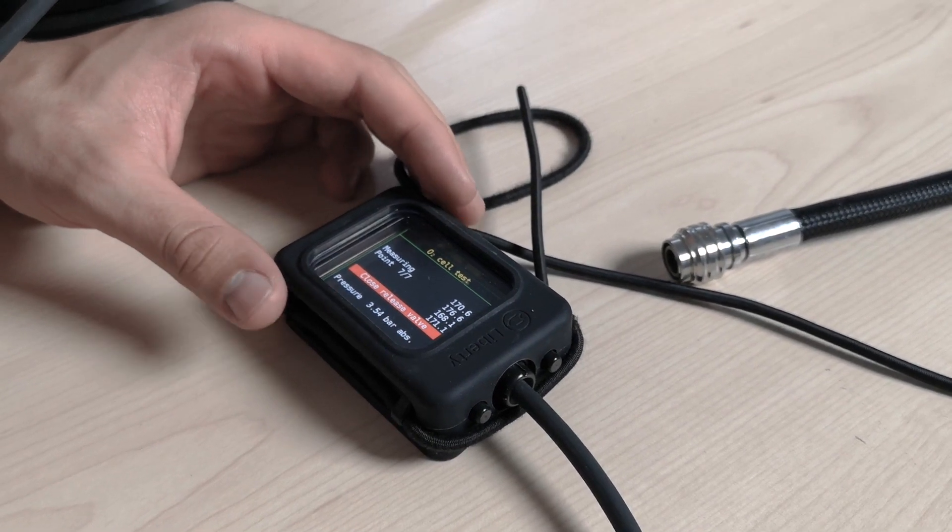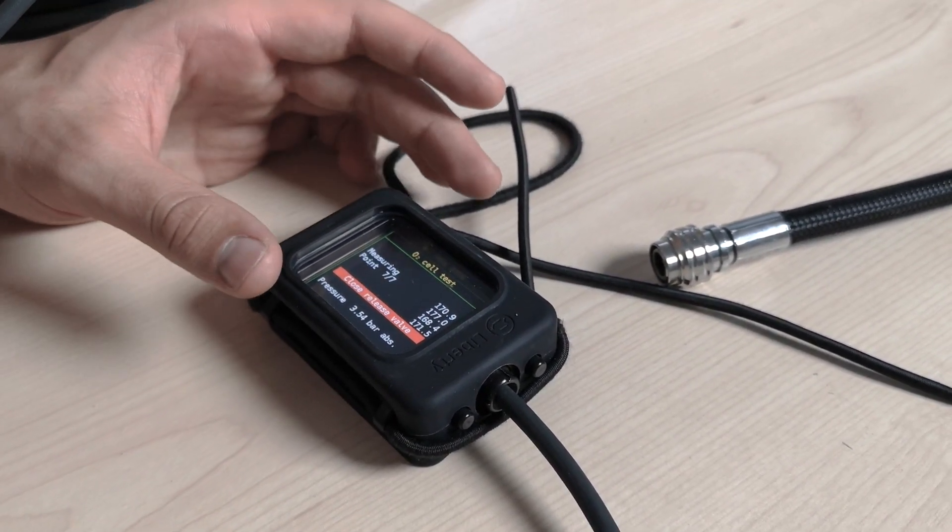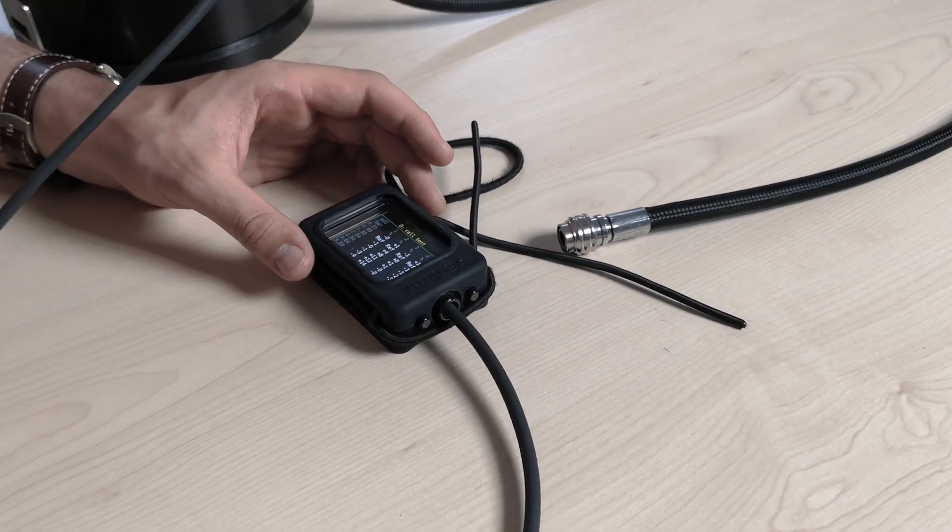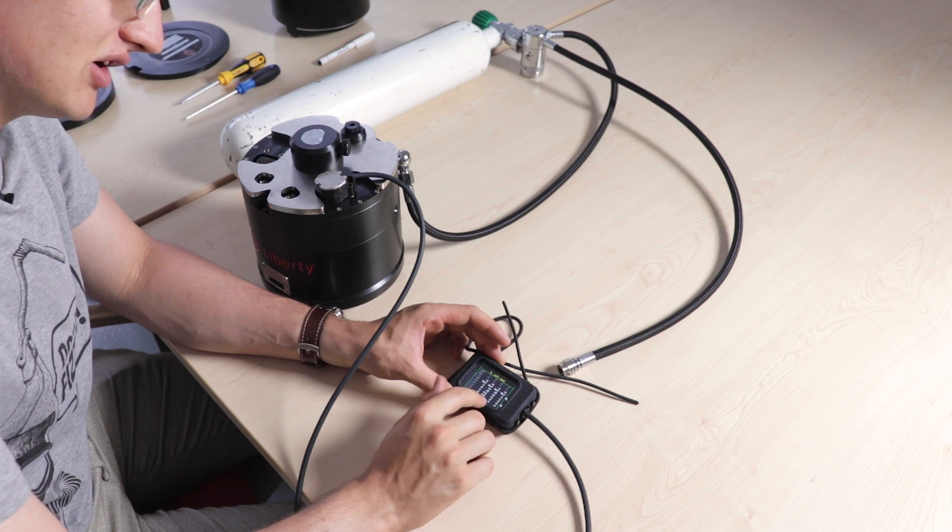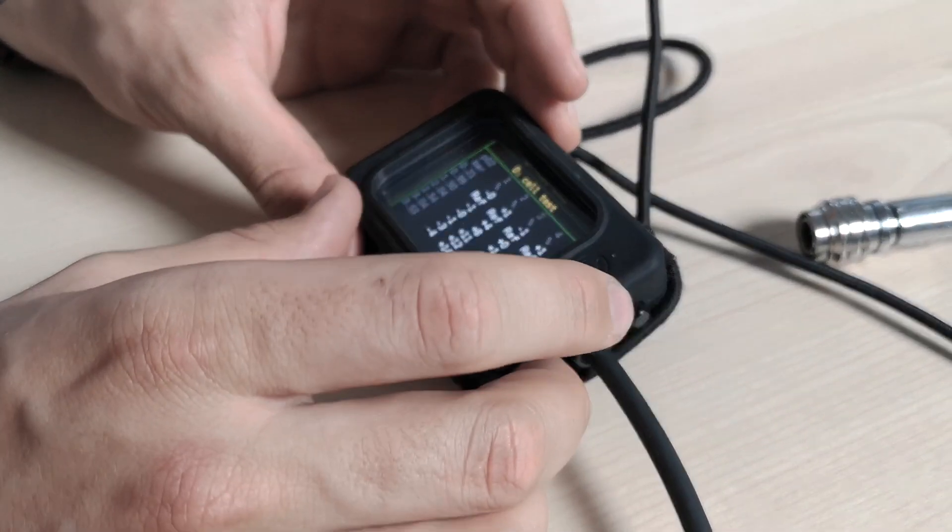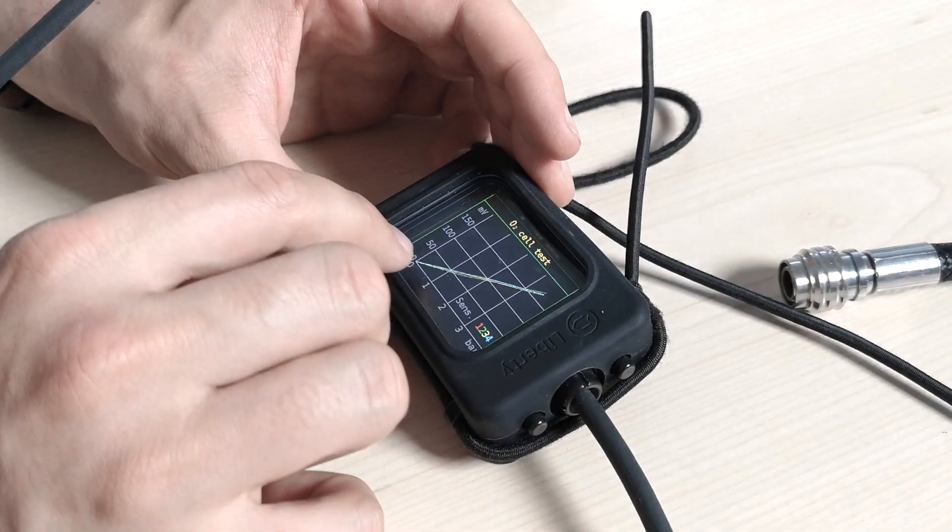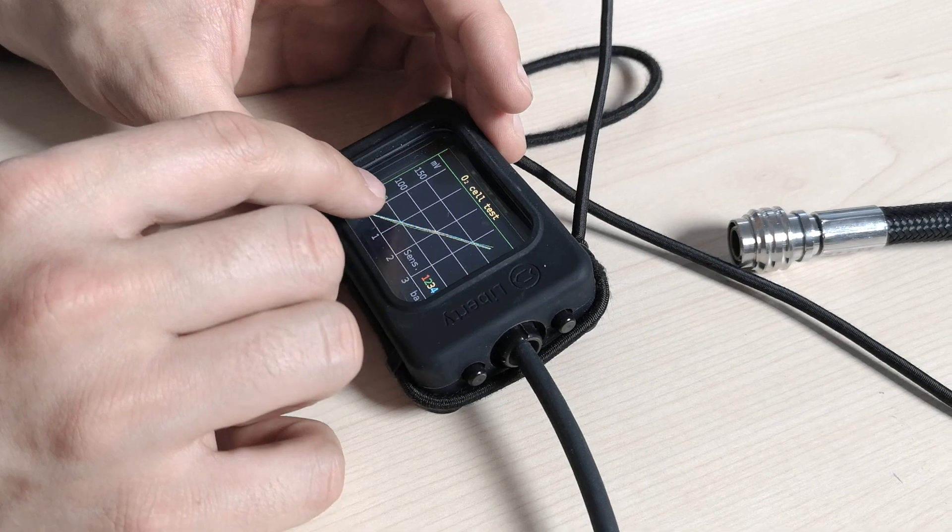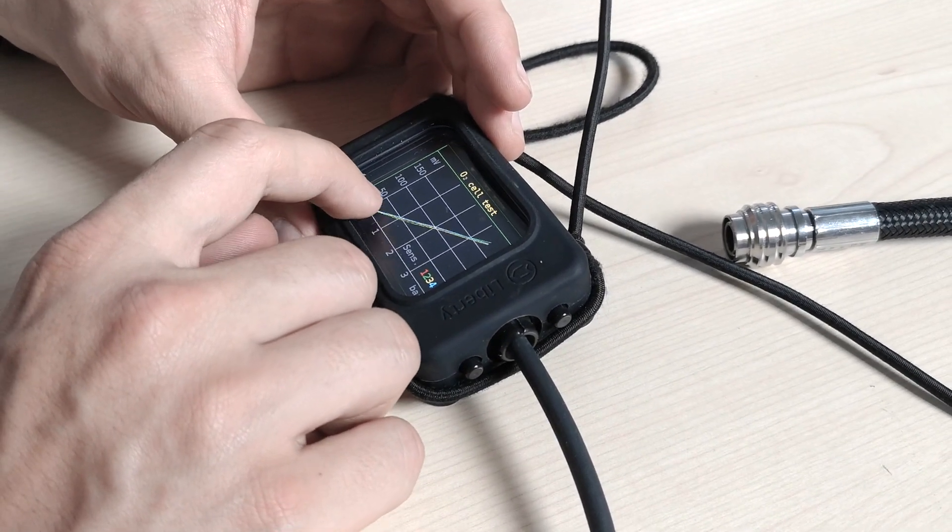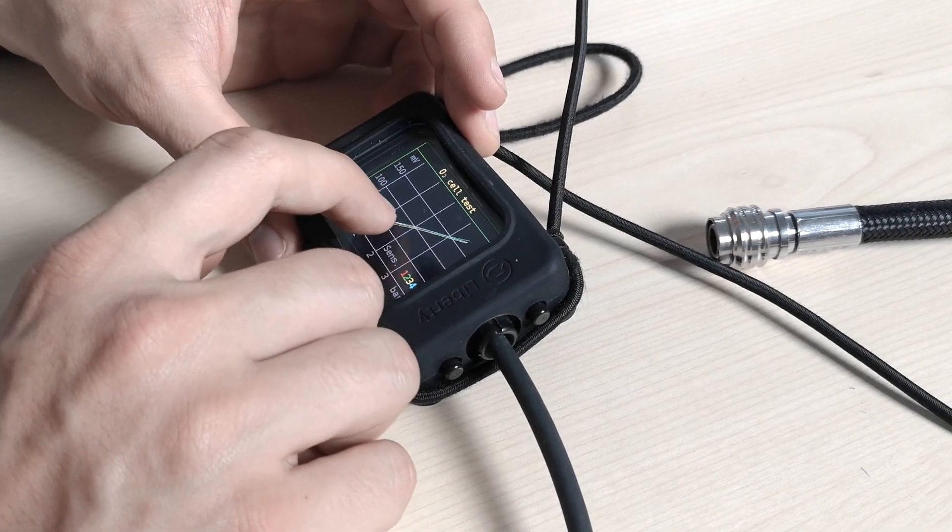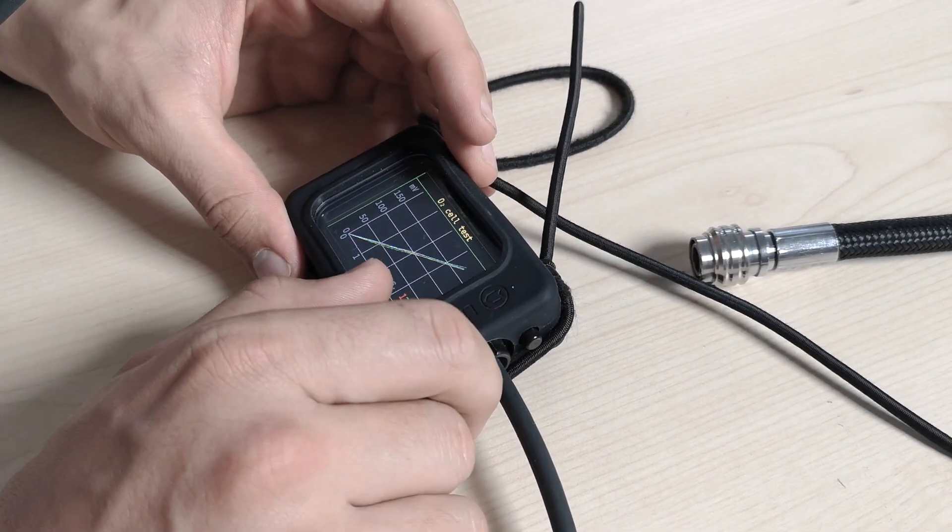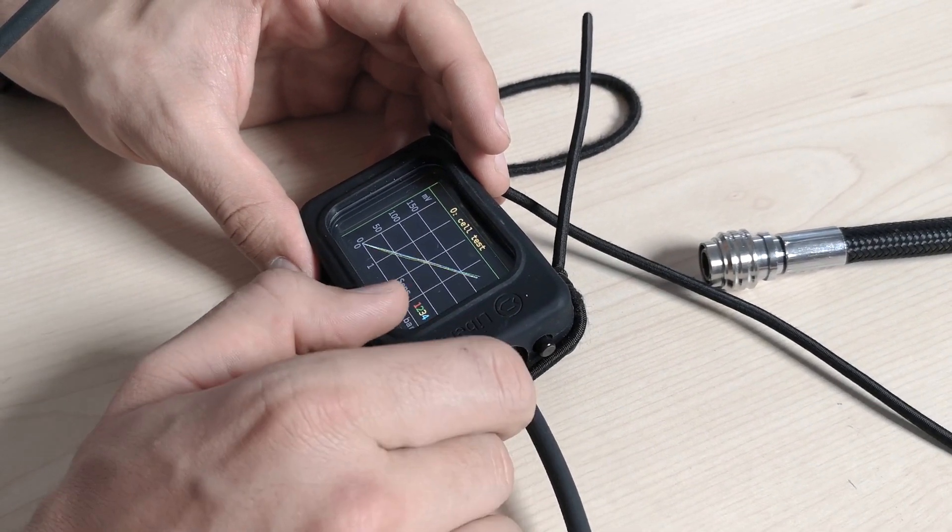It will know how the cell behaves at different pressures and can create a graph through this, showing you the deviation from normal at different pressures. This is the graph of your sensors, and you can see that none deviates too much. If one were deviating, it would look a bit like this. It will plateau at one point because it would not be able to reach the high potentials at higher oxygen pressures.